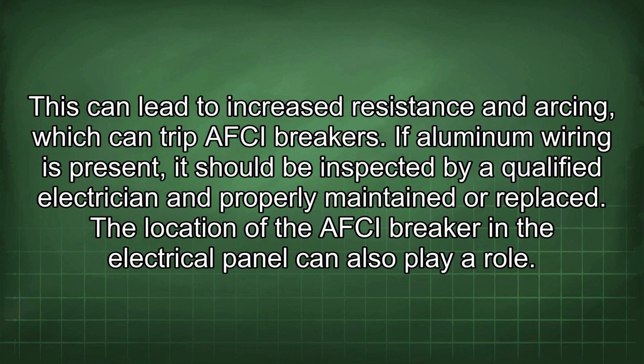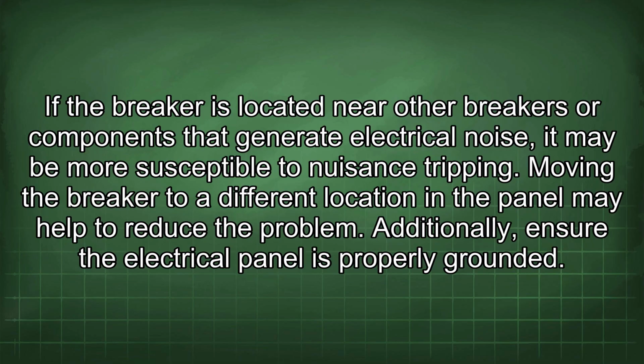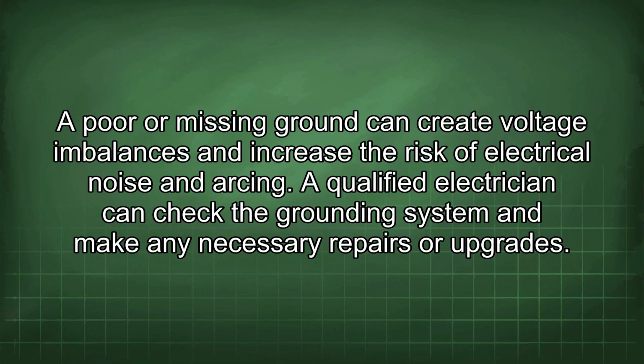The location of the AFCI breaker in the electrical panel can also play a role. If the breaker is located near other breakers or components that generate electrical noise, it may be more susceptible to nuisance tripping. Moving the breaker to a different location in the panel may help to reduce the problem. Additionally, ensure the electrical panel is properly grounded. A poor or missing ground can create voltage imbalances and increase the risk of electrical noise and arcing. A qualified electrician can check the grounding system and make any necessary repairs or upgrades.